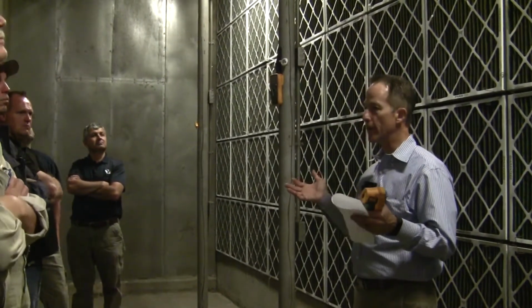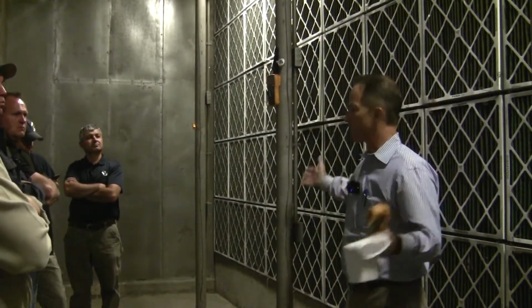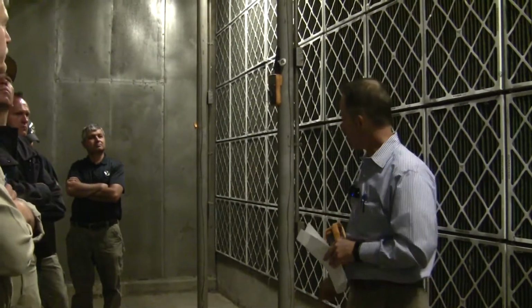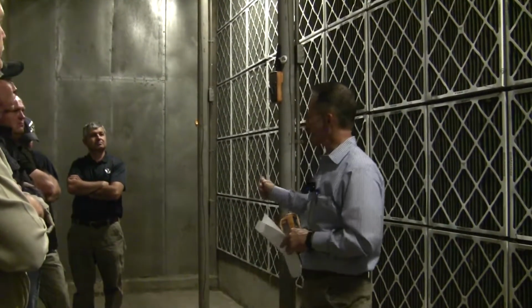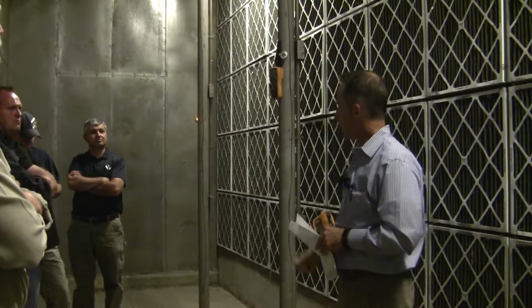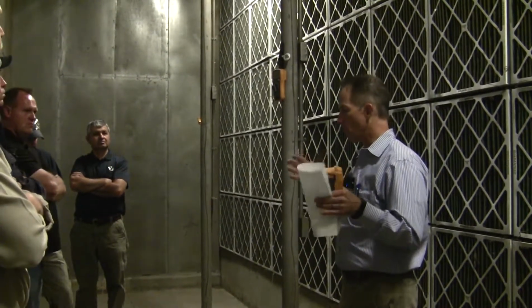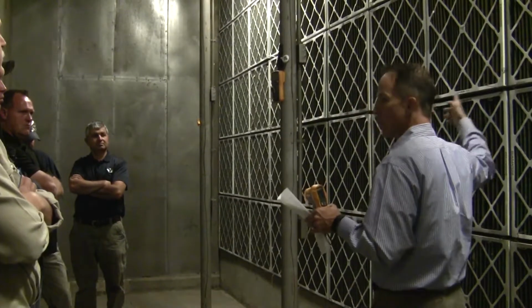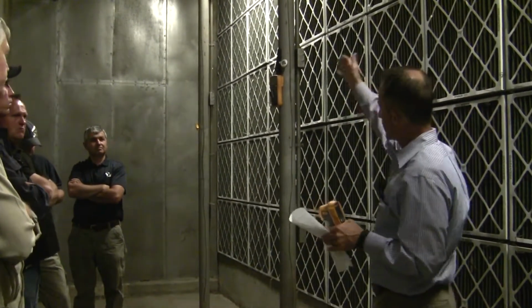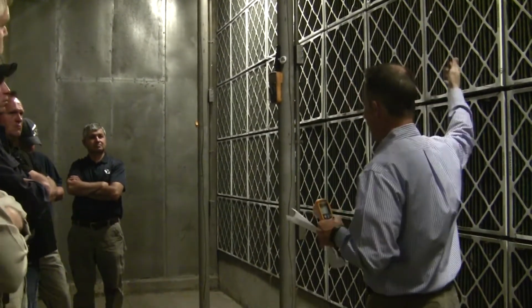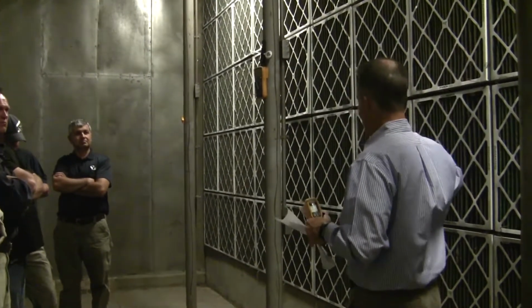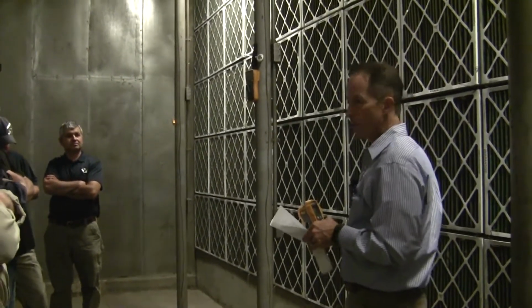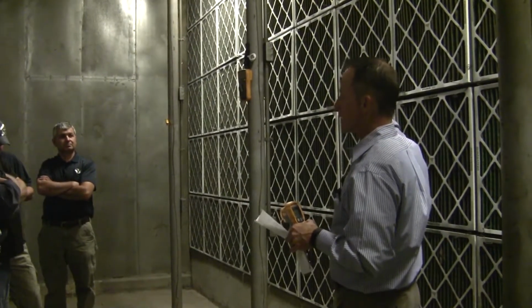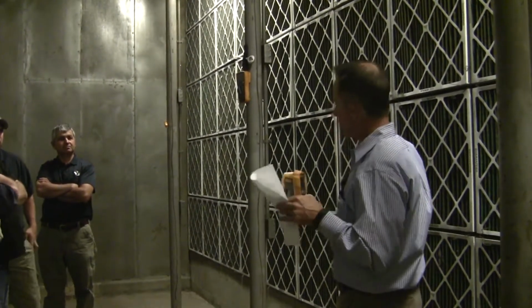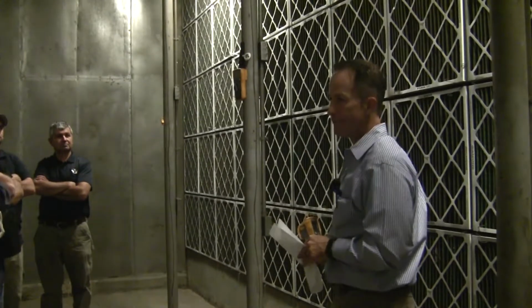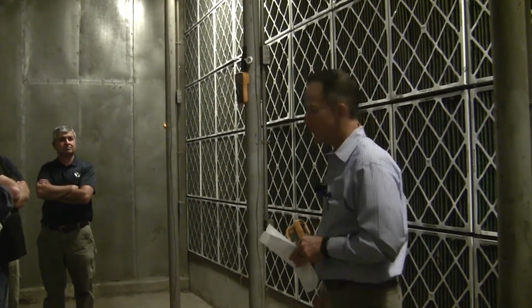Because you're going to have enough air in just the area covered by the sensors that a point sensor isn't going to get you the accuracy you need. What's more important is making sure we're consistent all the way through our air handler. So if I'm 73 here, I should be 73 all the way through. Going through the air handlers or the fans, maybe I come up a little bit, 73 and a half. If you're looking like that, it's beautiful, right? Just leave it and don't worry about it.